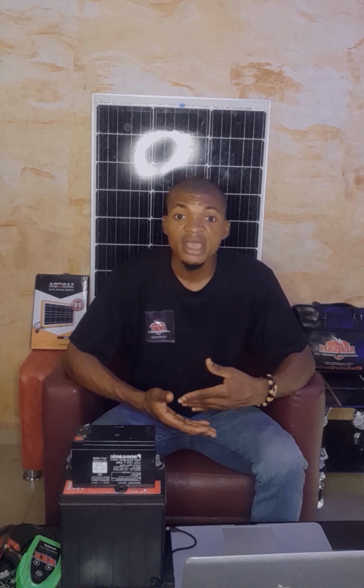For instance, you have a load of 1 kVA as calculated, so I am not meant to power it with exactly 1 kVA. So for me, I go above 1 kVA. So if I must start up the load, it must be from 1.2 kVA to 1500 watts, understand? So since I have gotten my VA to be 1000 VA, any inverter that I will use to start up a load of 1 kVA must be above 1 kVA. And when you do that, the system will serve you very well without problem. But when you start it with 1 kVA and your load is exactly 1 kVA, you see that any slightest addition of load will make the inverter trip.